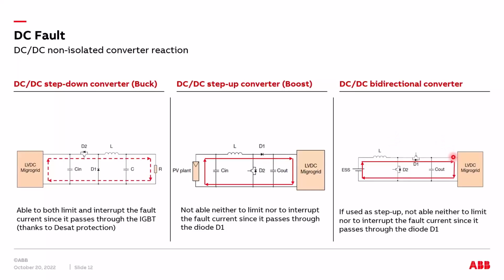The same thing if we have a bidirectional DC-DC converter, which is normally used in V2G applications, with the vehicle-to-grid function. So, in order to guarantee the injection of the power into the grid, we have to install the bidirectional AC-DC converter and also a DC-DC converter. So, if we have a fault on a DC microgrid in a step-up configuration, as you can see, according to the internal architecture of the converter, we cannot limit this contribution since the current during the fault is passing through the diode D1. So in the second and the third configuration, we have to install on the left or on the right, this means on the input or on the output of our converter, a suitable protective device in order to be able to detect and interrupt this contribution.